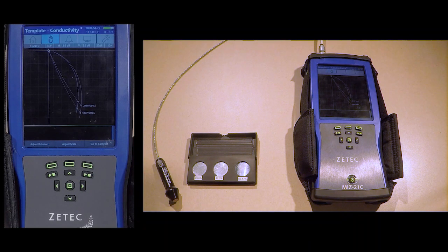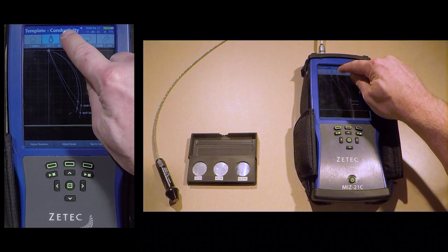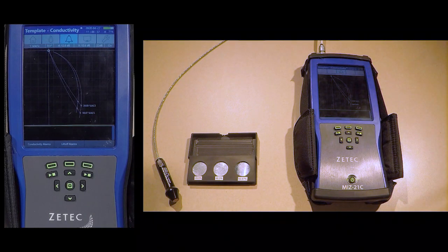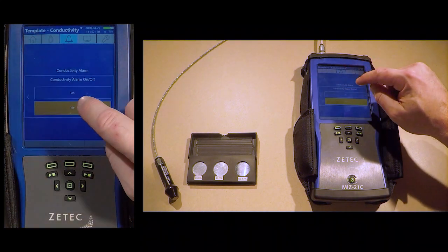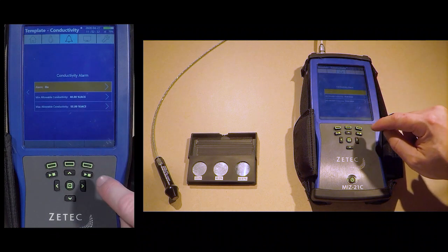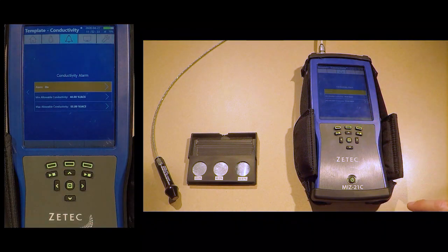To set the alarm, press the Stop Play button if necessary to stop acquisition. Tap the alarm icon. Use the menu items in the lower left of the screen to set your upper and lower limits for both the conductivity IACS and, if desired, coating thickness.